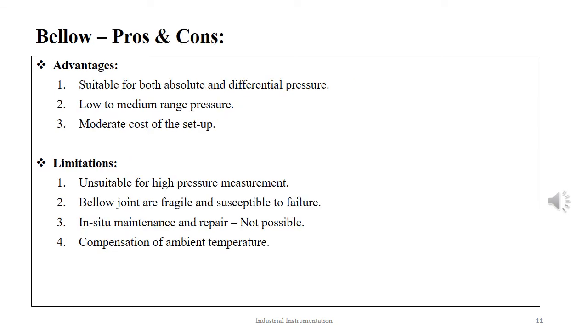The advantages that a bellow offers are that it is capable of measuring both absolute and differential pressure. It is used in measuring low to medium range pressure. The cost is moderate to low. The limitations of the bellow are that it is not capable of measuring high pressure. Bellow joints are fragile and susceptible to catastrophic failures. In situ maintenance and repair is not possible in bellows. It requires ambient temperature compensation.